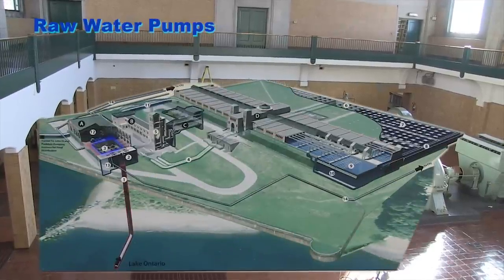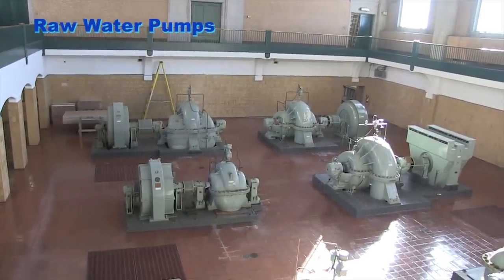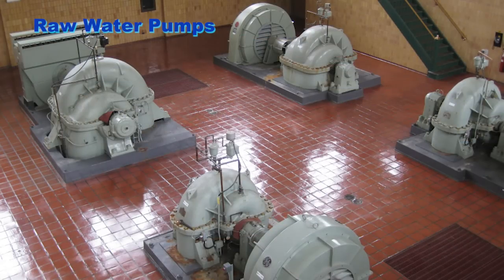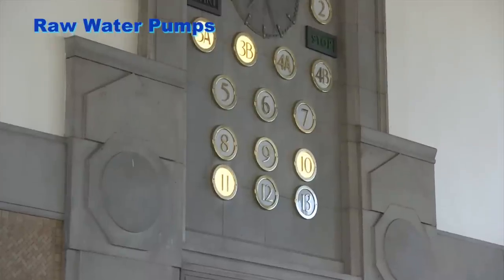Raw water pumps. One 115 MLD, one 180 MLD, one 238 MLD, and three 275 MLD pumps lift the water from the lake to the mixing chambers at the north end of the plant, from which it flows by gravity through the rest of the process. The two intake mouths are supported by three pumps each. Pumps 8, 9, 10, and 11, 12, 13 are for the intake flumes. Pumps 1 to 4 are for treated water distribution. Pumps 5 to 7 pump treated water back up to the backwash filters. Pumps 10 and 11 are in operation for the intake flumes, and pumps 3A and 3B are for the treated water distribution.